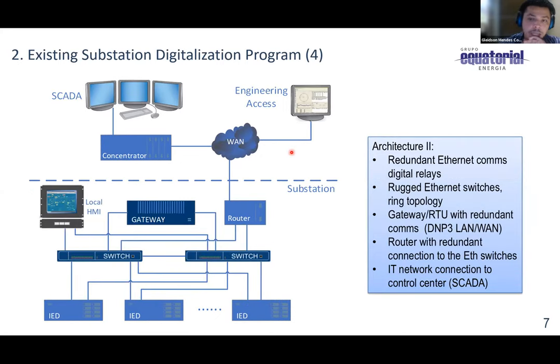And this problem was solved in architecture 2, where we had Ethernet digital relays, where we could have redundancy on our substation. So even if the relay has two ports, A and B, the two ports can do the same thing. So I have many protocols in the same connection, the same physical link between the IED and the switch. So here port A is connected to switch A and port B is connected to switch B. If I lose switch A, I still have the monitoring and the engineering access through the same physical link. This is the redundancy that we have on our substations.